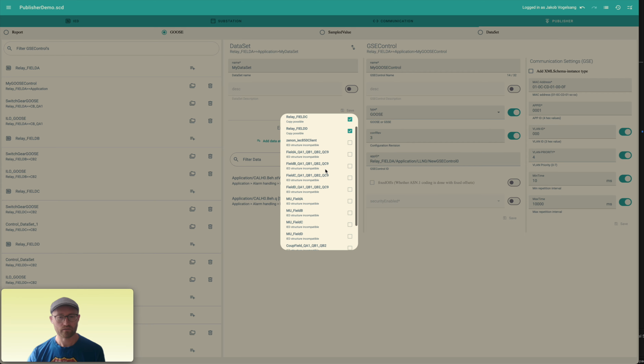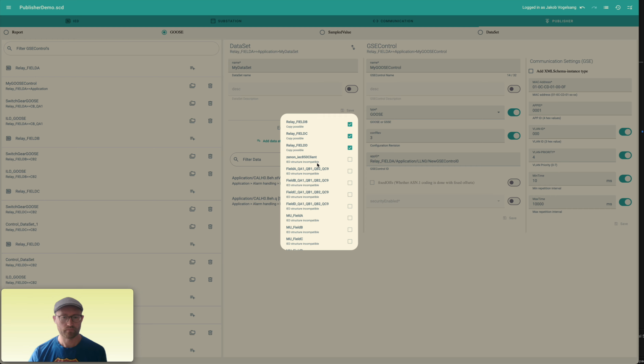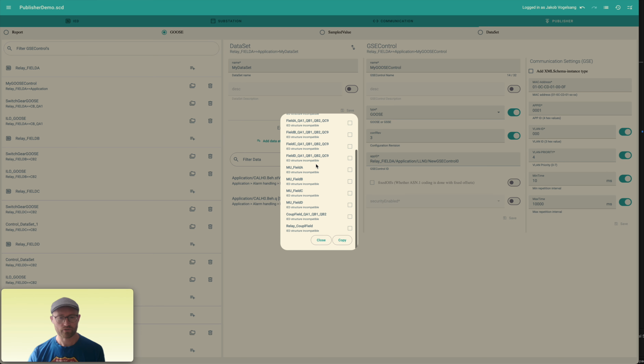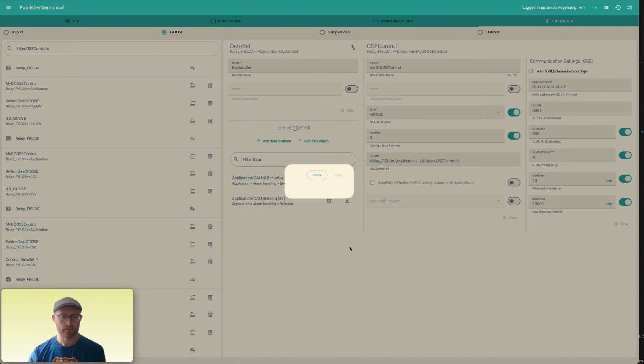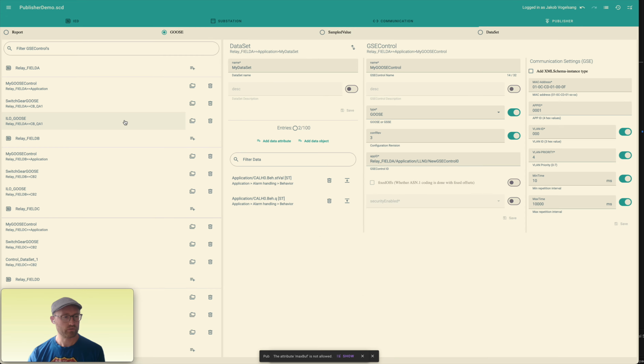And if these checks are true for an IED, you can select and deselect it. If not, you see the information that the IED structure is incomplete. It'll also check whether such a goose already exists in the other IED to make sure that the naming restrictions in the schema are met. And then if you've done so, you can copy over the goose into other IEDs.